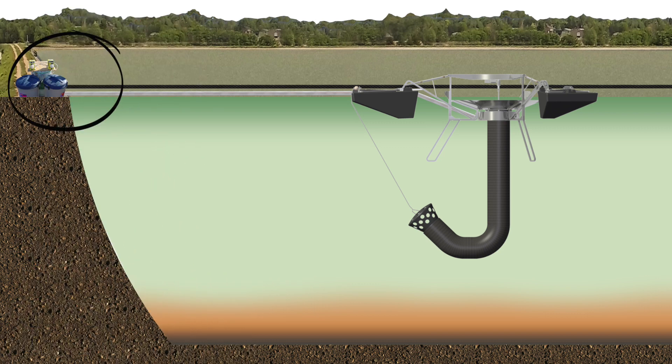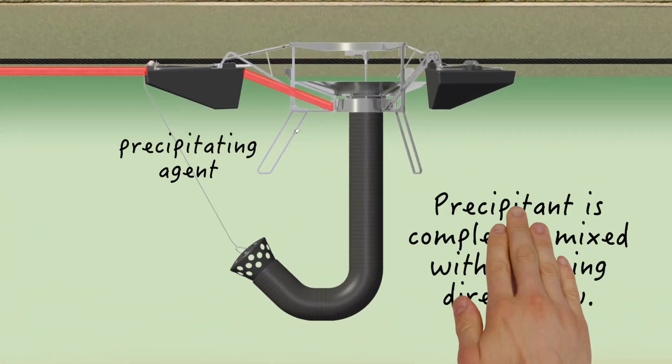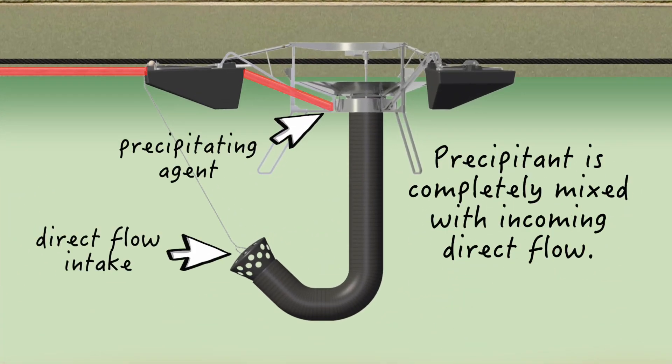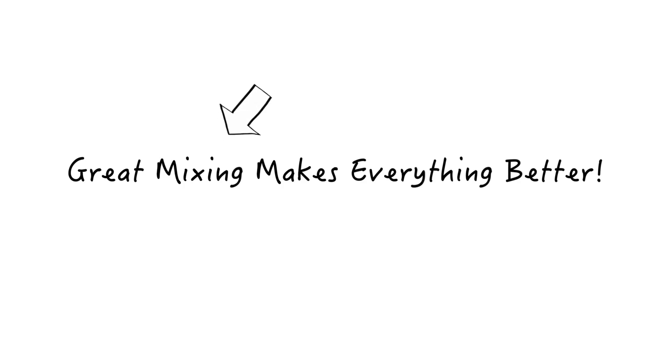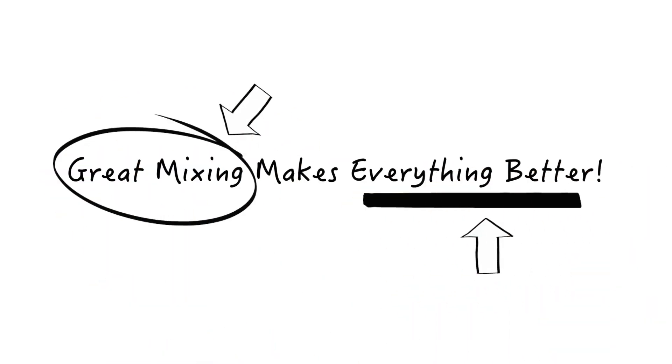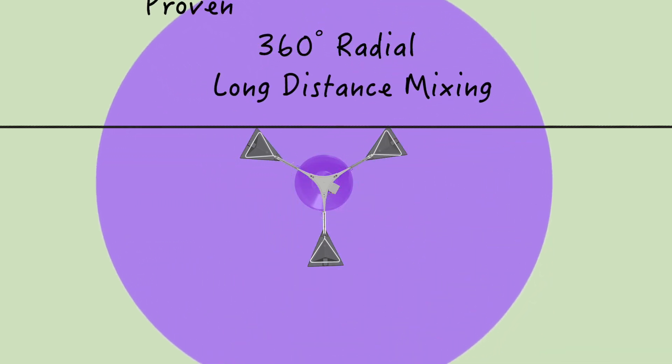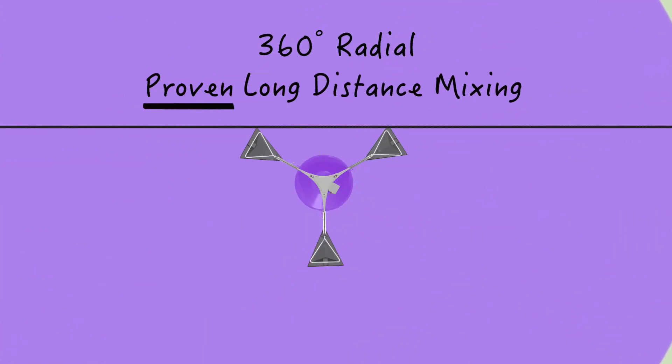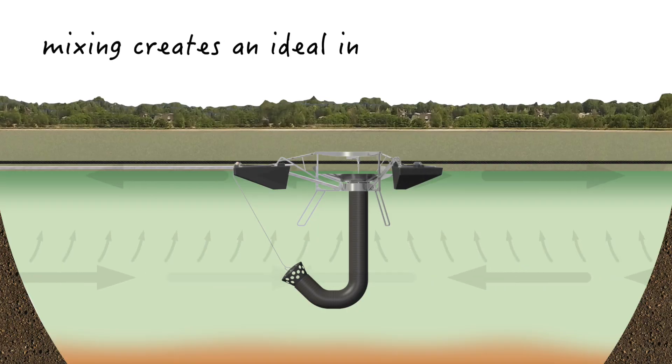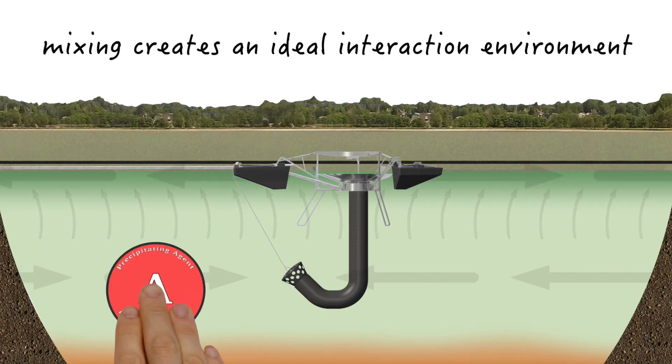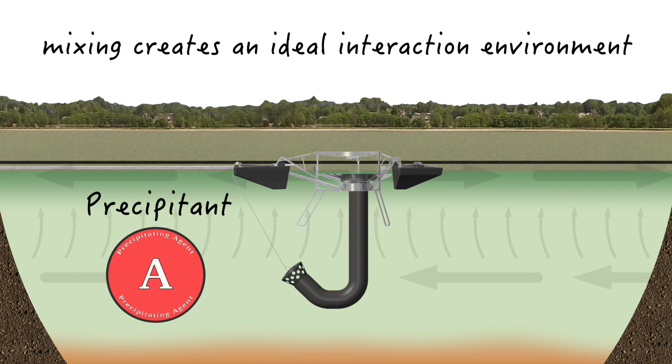The phosphorus precipitating agent is sent from the onshore metering system down the injection hose to the machine just below the impeller. Here, the precipitating agent is fully mixed into the entire direct flow of the floating wastewater mixer. And this is where great mixing takes center stage. The well-mixed precipitant is then distributed radially across the lagoon, utilizing proven long-distance circulation technology. It creates an ideal interaction environment between your precipitating agent and the target phosphorus.